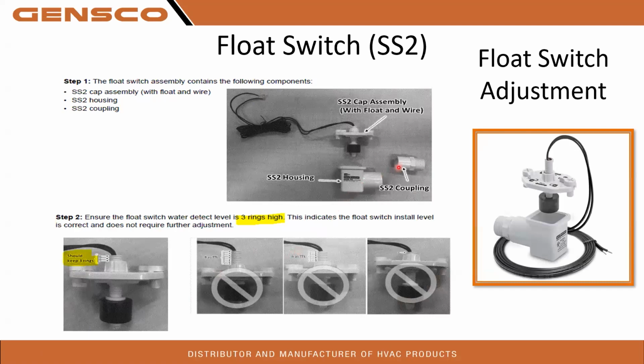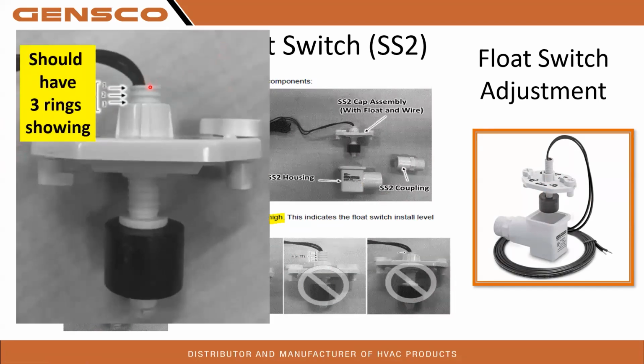In the float switch, there is an adjustment on the top of it to adjust that float up and down. The proper adjustment for this, why it's not set up from the factory, I'm not sure, but it should be 3 rings high. If you're looking at the top of the plate there, once it's all mounted up, you should only see 3 thread rings sticking out of the top. That is properly adjusted. Make sure that is set up. Here's a nice close-up view of those 3 rings.